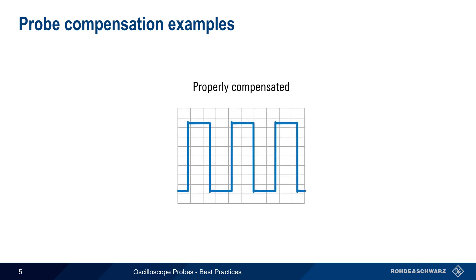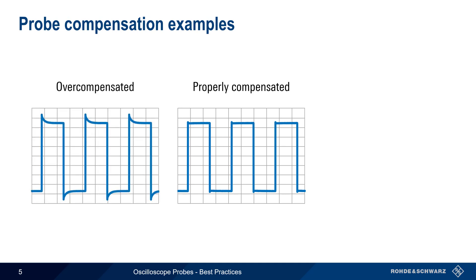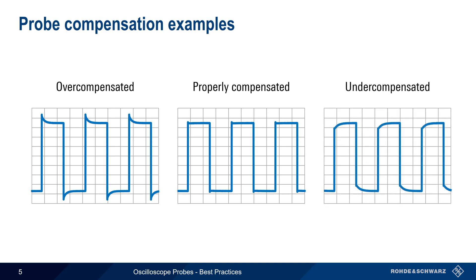A probe is properly compensated when the tops of the displayed compensation signal are essentially horizontal. Overcompensated probes create overshoot on the leading edge of the signal, and undercompensated probes cause undershoot on the leading edge. The compensation capacitor is adjusted until the waveform has rectangular edges, which usually only takes a small fraction of a turn.